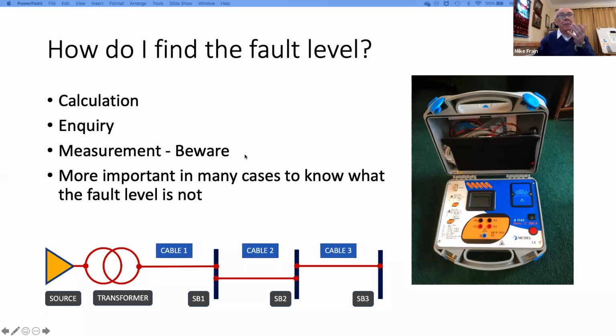So I keep talking about fault level, but the question is, well, how do you find it? Well, another part of the practical guidance that I gave is to try and tell you how to get it and how important it might be that we have accurate figures in there. And the first thing is by calculation. In order to carry out calculations, you need to know the prospective short circuit current at the equipment to be worked on, don't we, at that point?